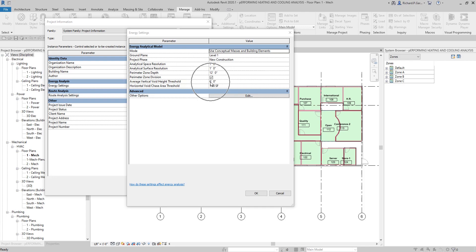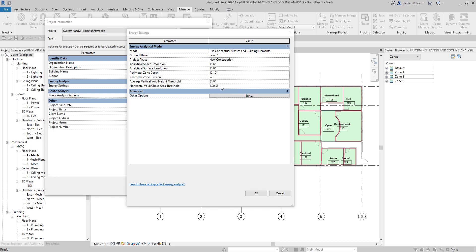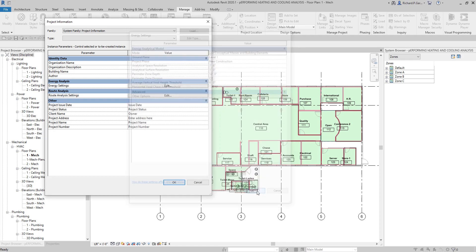The default is six feet. You also have the Horizontal Void Chase Area Threshold, which is similar to the Average Vertical Void Height Threshold. This value is used to avoid the application of unwanted thermal loads and properties to analytical spaces. When an analytical space's area falls within this threshold, it will also be assigned to unconditioned zone equipment for exclusion from any systems analysis. I'll select OK after using the default settings.